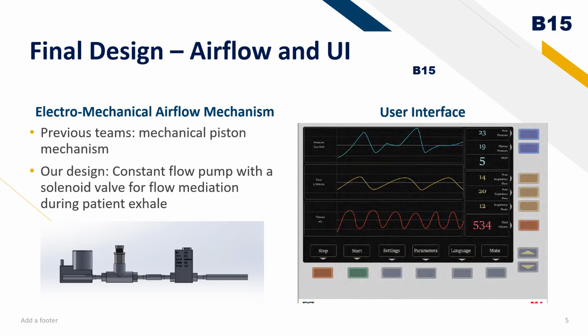Our mechanism is made up of a constantly running pump that connects to a solenoid valve that, when closed, stops air from reaching the patient as they passively exhale, and when open, allows the air to reach the patient as they inhale. We found that leaving the pump on and mediating the air with the solenoid valve would be more efficient than both the mechanical piston and having the pump turn on and off with the patient's breath cycle.